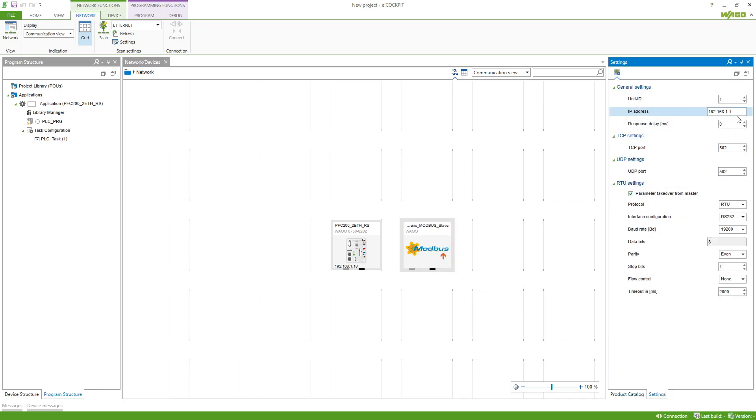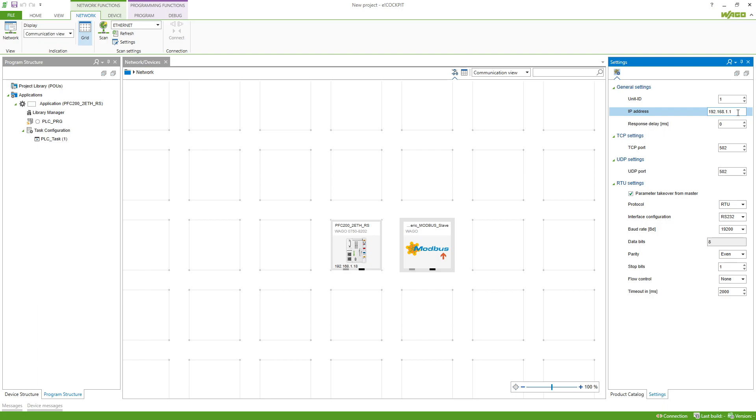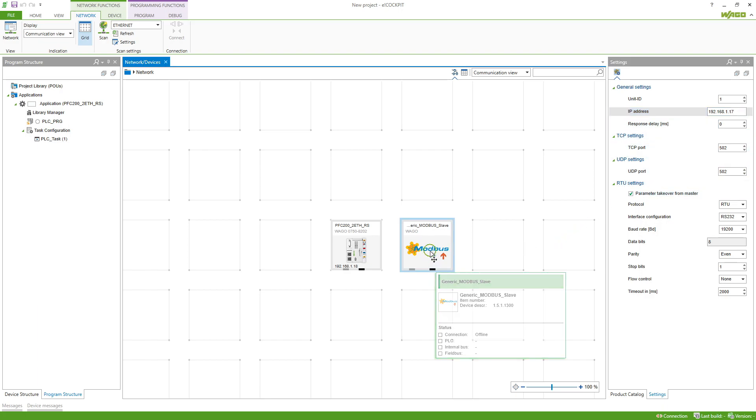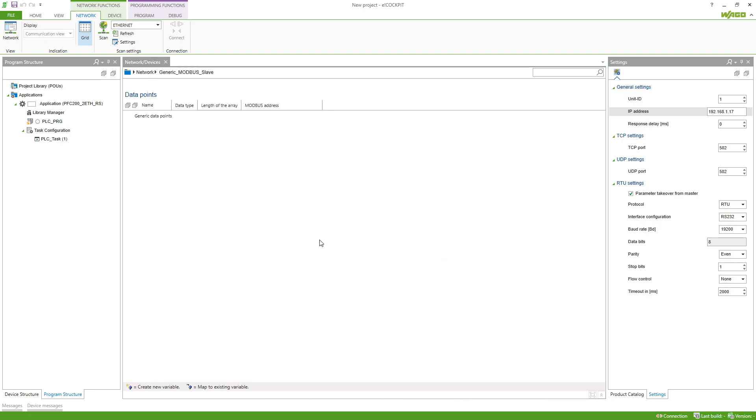In the settings we set it to the IP address our slave has. In my case this is the 1.17. If we do a double click on the Modbus slave we can recreate the data points which this Modbus slave has. Mostly you will get those from the manual of the Modbus slave.